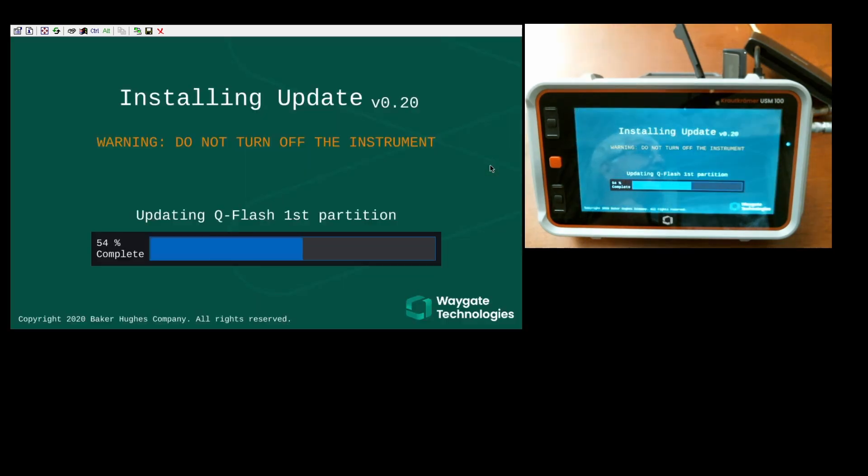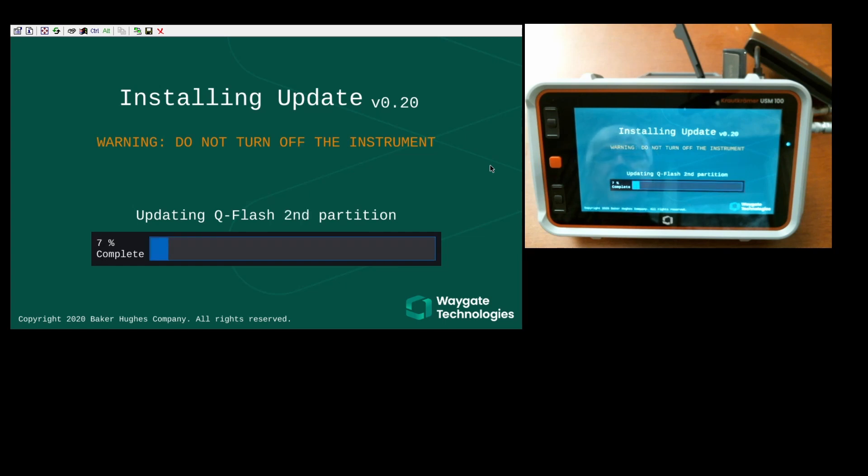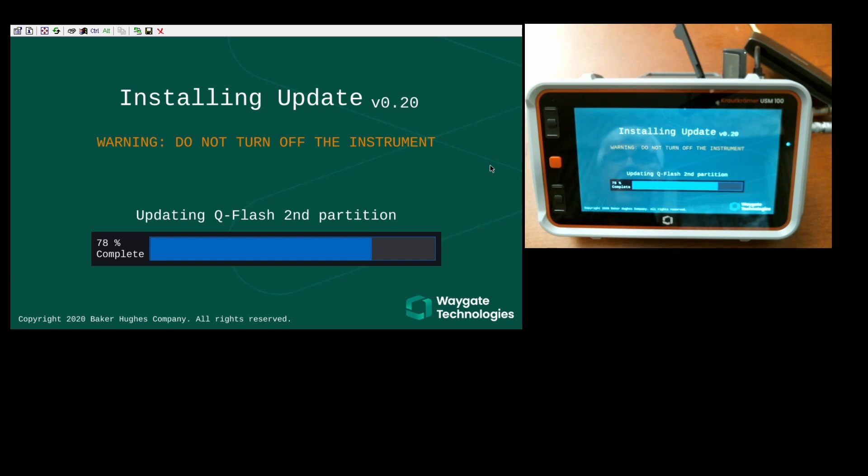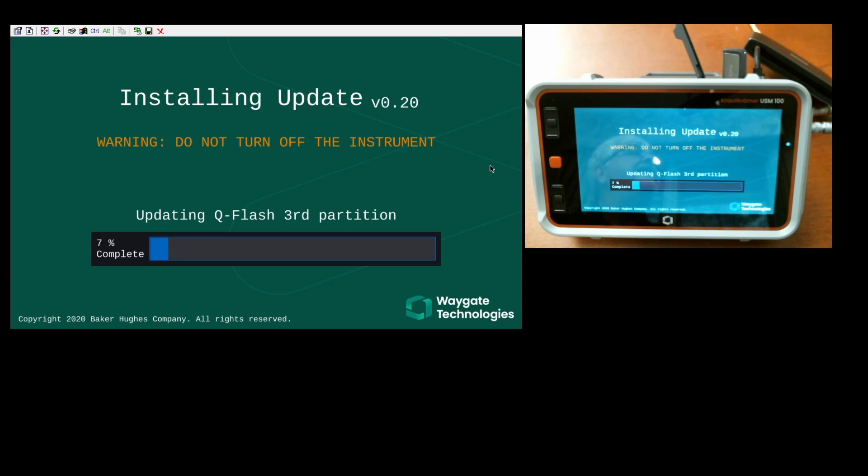OK, now we see that the instrument has finished analyzing the update file, and it's begun the installation process. You'll see the regular software closes, and the update installer begins to run. There'll be a series of screens like this. You'll see progress bar. It'll tell you that it's installing the update. It goes through several steps of this. There are many pieces of memory to update in the instrument, along with the main hard drive. So this process generally takes 10 to 15 minutes to complete. Again, we're going to speed through this section, cut some time out and accelerate things. We'll catch up here in about 15 minutes.